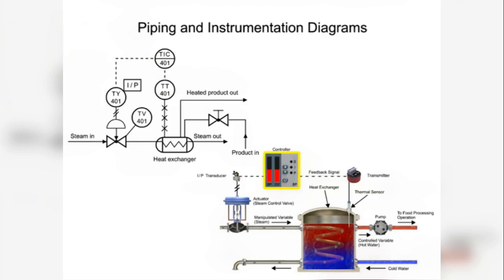The controller and indicator is the instrument where the transmitter sends an electrical signal, and is shown in the functional identifier at the second and third letters, I and C. Balloons with a solid dividing line indicates that the instrument is board mounted.